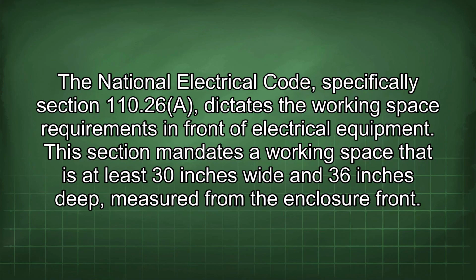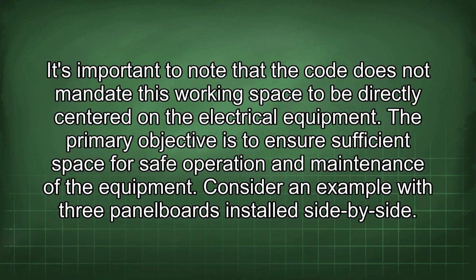The National Electrical Code, specifically Section 110.26(A), dictates the working space requirements in front of electrical equipment. This section mandates a working space that is at least 30 inches wide and 36 inches deep, measured from the enclosure front. It's important to note that the code does not mandate this working space to be directly centered on the electrical equipment. The primary objective is to ensure sufficient space for safe operation and maintenance of the equipment.